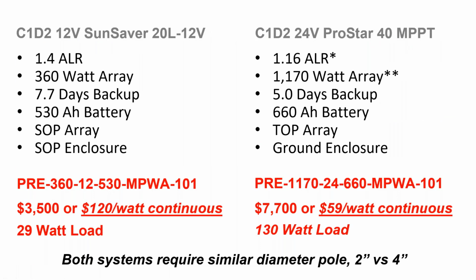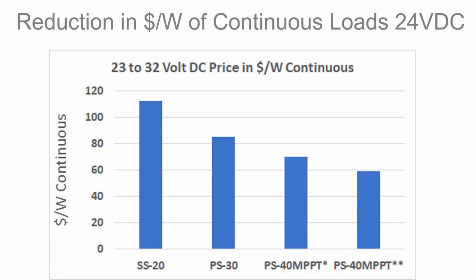So in summary, going from our Sunsaver 12 volt 20L design, we supported a 29 watt load at about $120 per watt of continuous load supported. Now moving up to a C1D2 24 volt ProStar 40 amp MPPT, we're supporting at the upper end of our comfort limit with an MPPT, a 130 watt load, coming all the way down to $59 per watt continuous - more than half reduction in the overall cost per watt of supporting a Class 1 Division 2 system for a HAZLOC load. This summarizes, at least at 24 volts, the reduction in dollars per watt of continuous load operation for these systems.